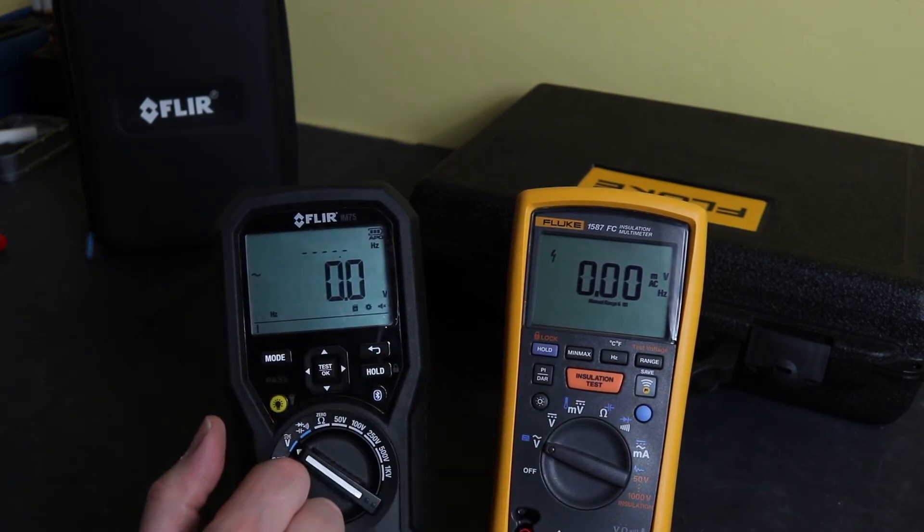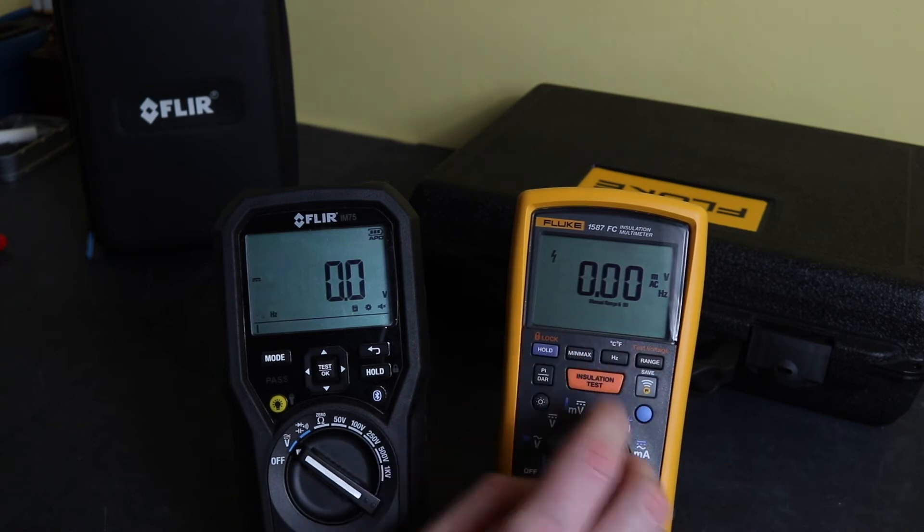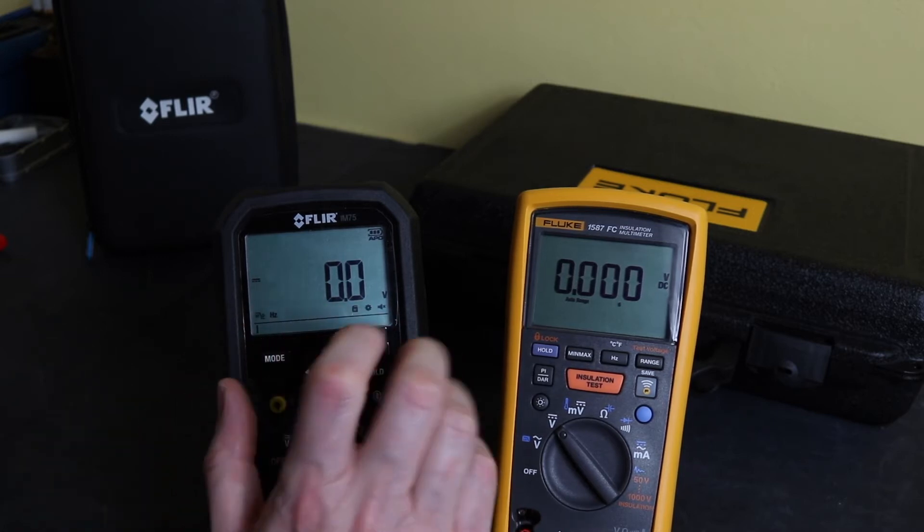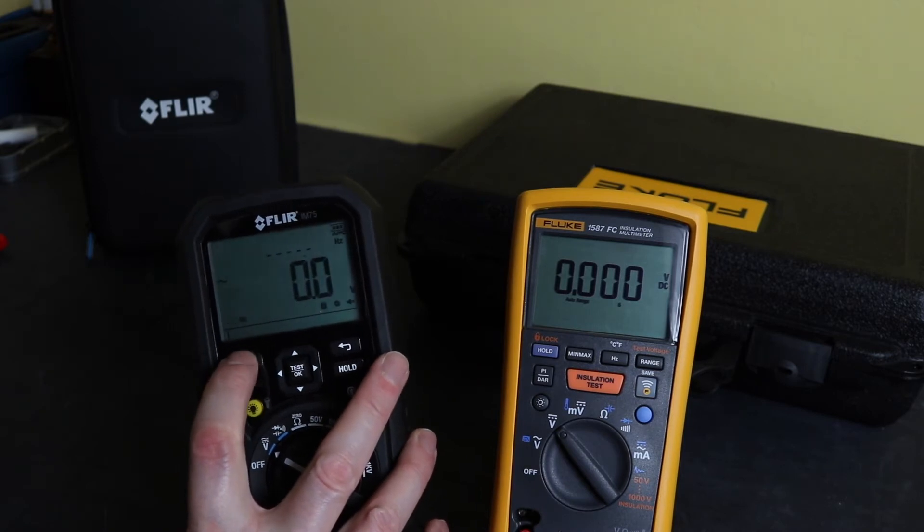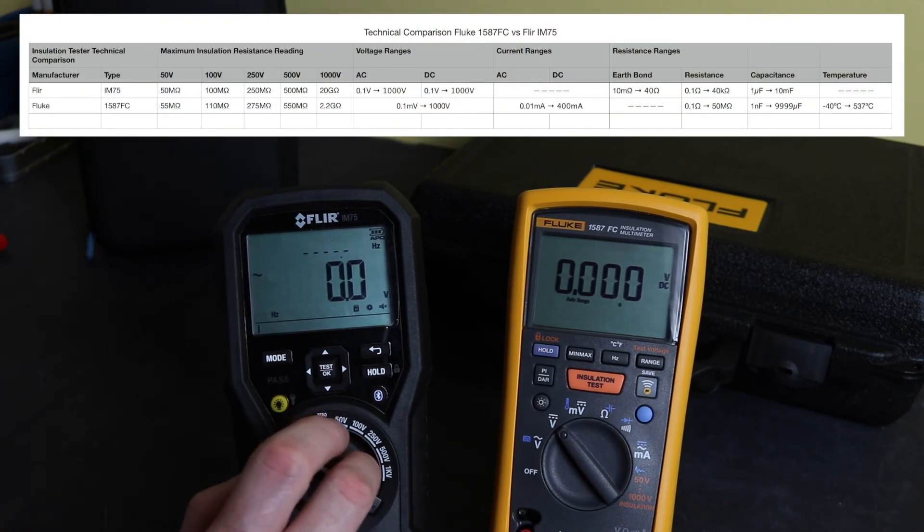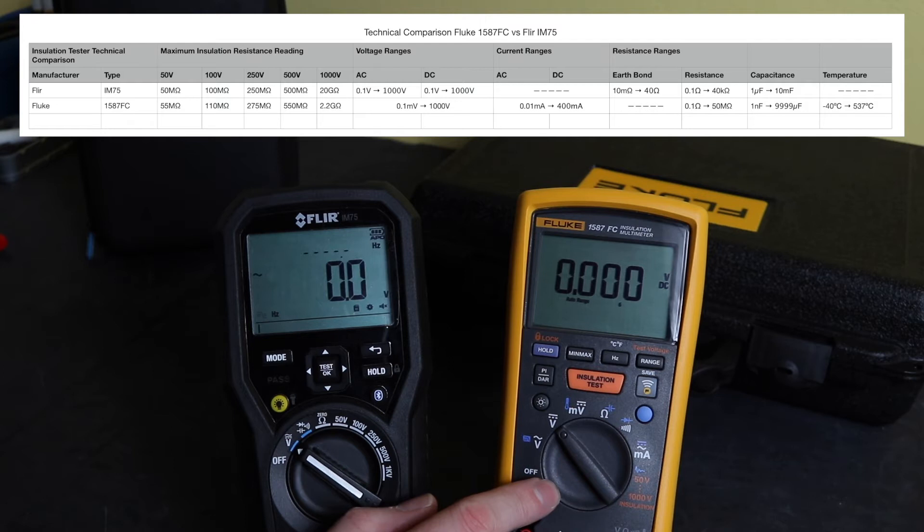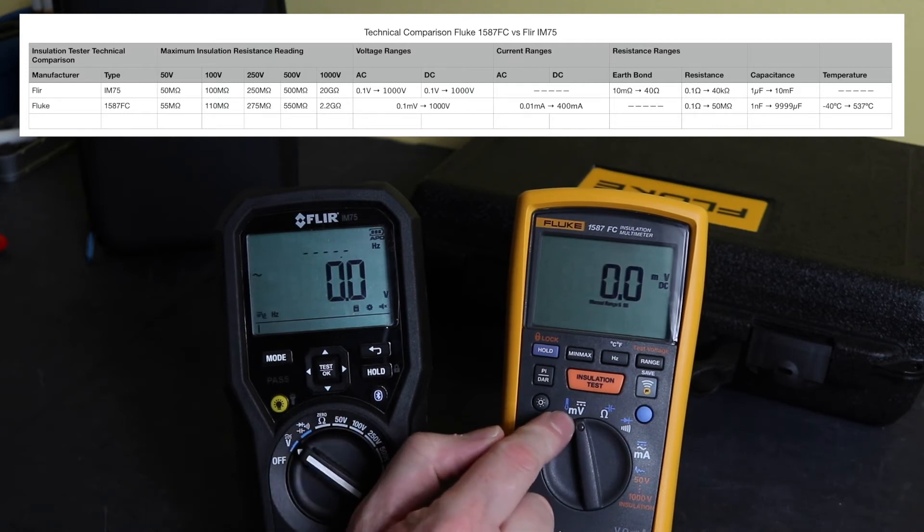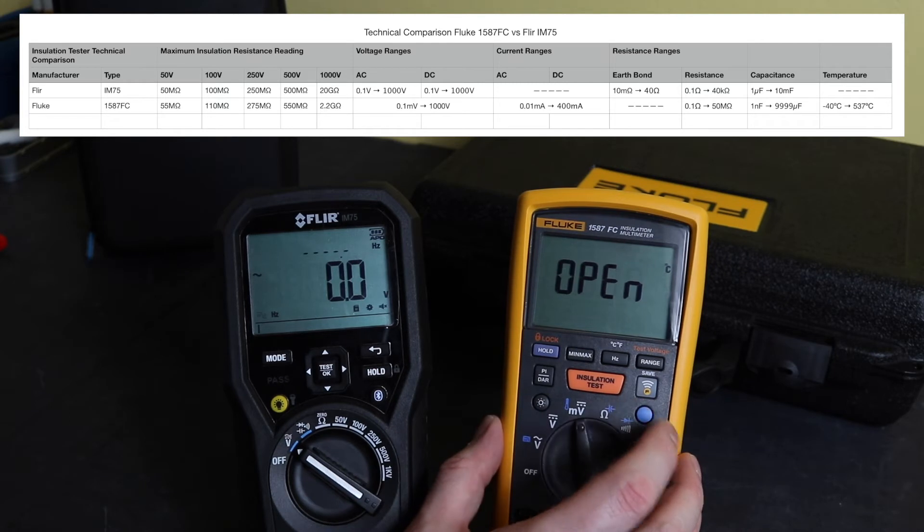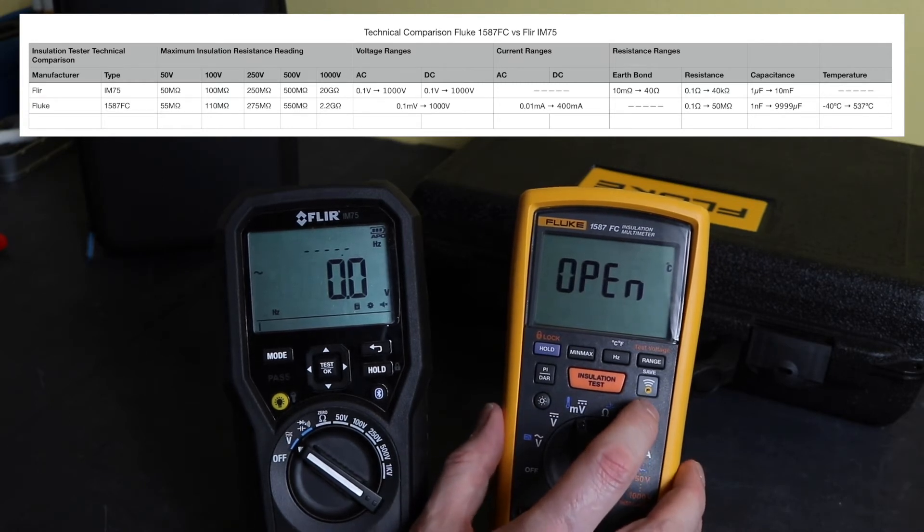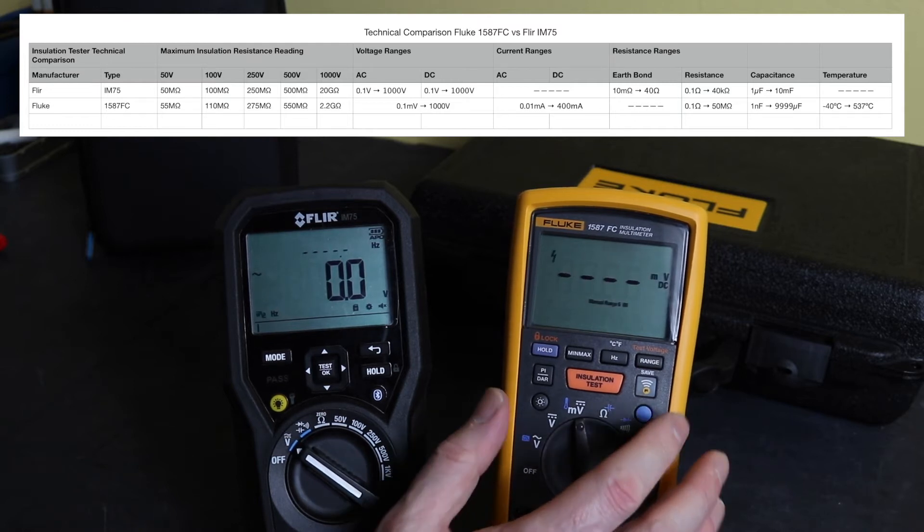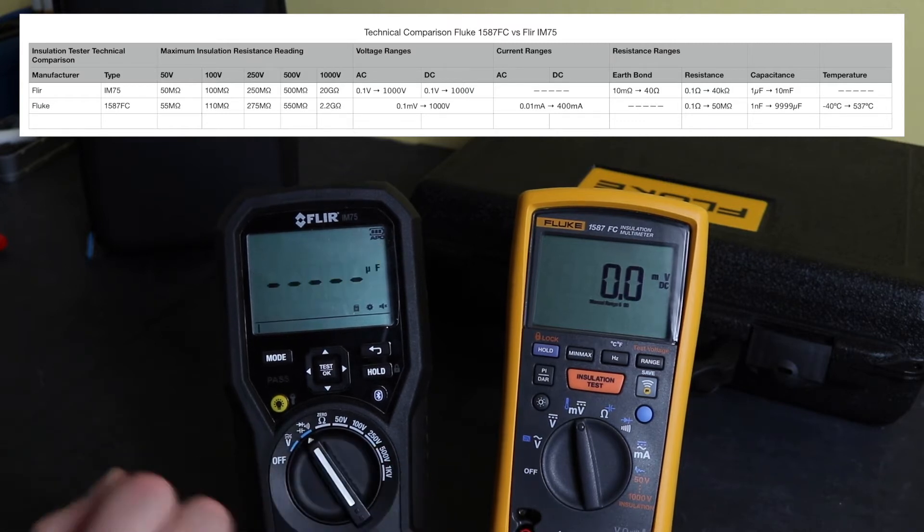To get to DC function on the Fluke here, that's a separate position on the function switch. And on the Flir here you can just take it through the mode, AC and DC, to switch between the two. Range-wise, the Flir is 100 millivolts to 1000 volts, both AC and DC. The Fluke is 0.1 millivolts AC and DC, but to get down to the millivolts you actually have to flick this round to the next function position, which is DC millivolts there only. And you also have the option to take to the temperature range on this instrument when you're in the millivolt function. Temperature-wise it will read minus 40 degrees C to 537 degrees C. As I said earlier, no temperature measurement capability on the Flir here.